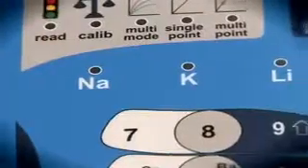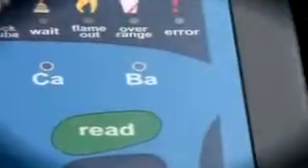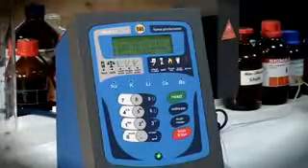There are two icons following the mnemonic representing the ion on the LCD display. The first displays a representation of the graph of the concentration of the ion. A line angled forward indicates that the concentration is increasing. A line angled backwards indicates that the concentration is decreasing. A flat line indicates that the concentration is stable. A reading should only be taken when there is a flat line.